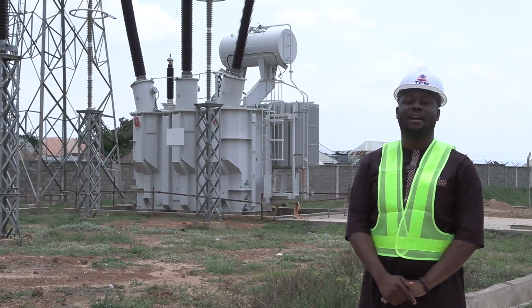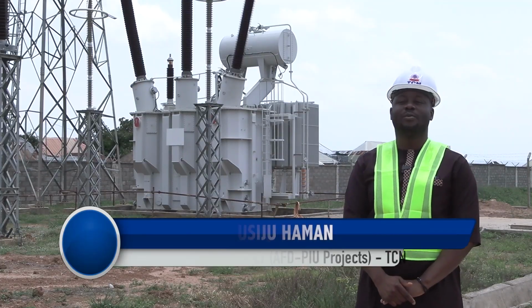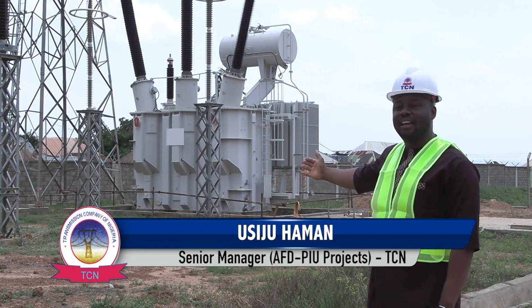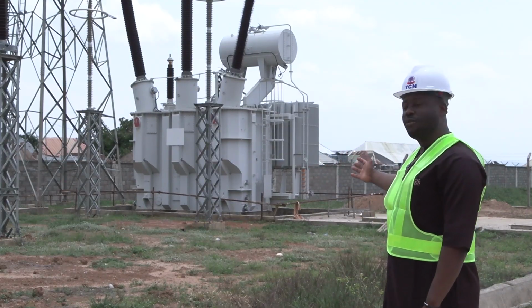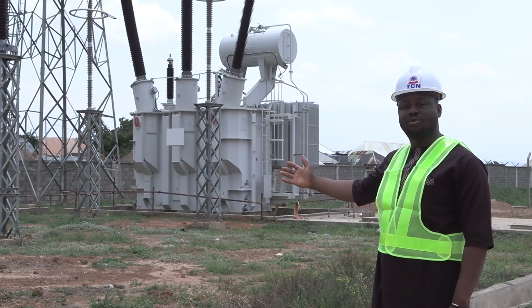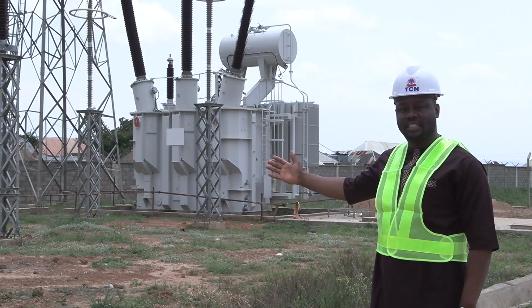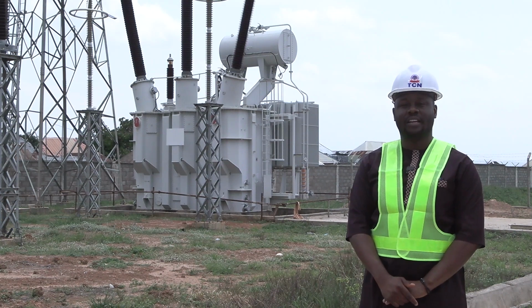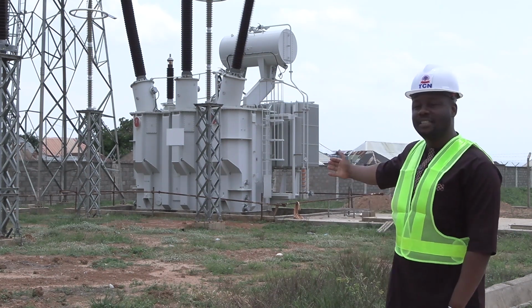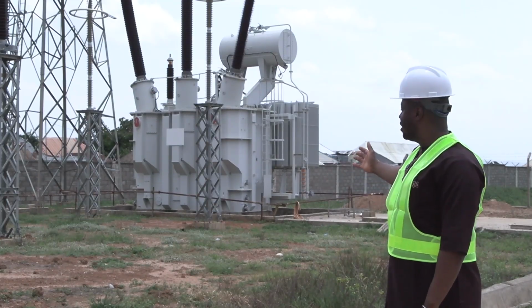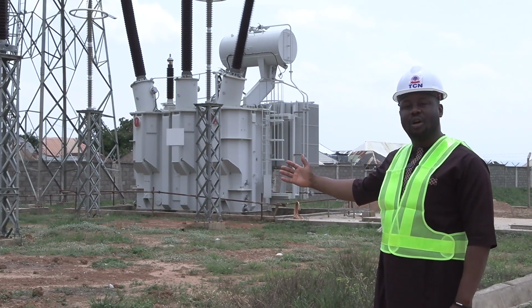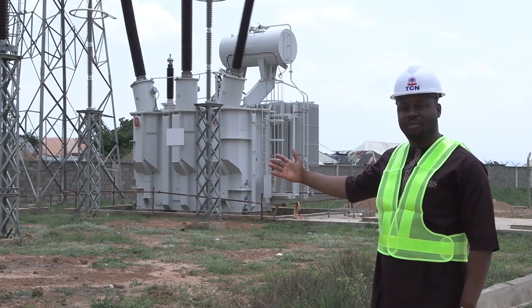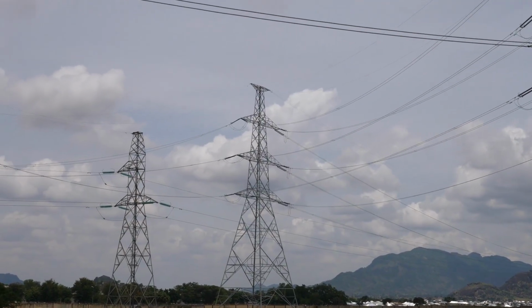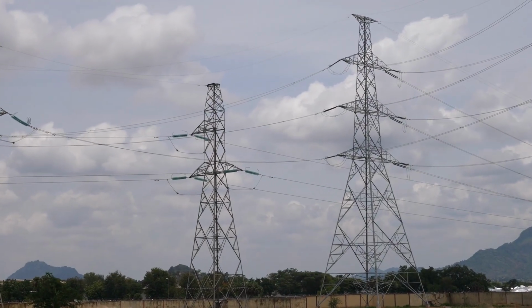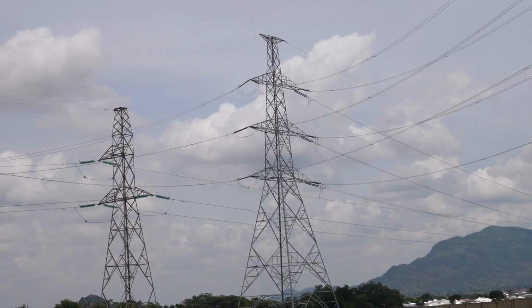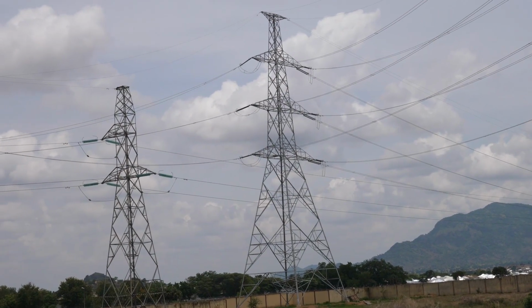Aside from the 2x150 MVA auto transformer, we also have a 1x75 MVAR reactor. This reactor is for voltage control, which is connected to our two 330 kV transmission buses in the station. The TCN official further stated that the reactor is meant to regulate the voltage level on the 330 kV transmission line from the 330 kV Kokolada substation in the Federal Capital Territory, FCT. The 330 kV Kokolada substation simultaneously takes bulk power coming from the Shiroro axis in Niger State and from the Lokoja axis in Kogi State.